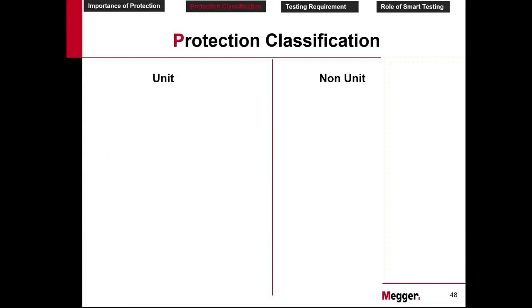So let's come back to this. You can keep this example to understand this protection classification. It's very easy. The security we are talking about is actually the relay. The relay is a protection device. It's going to protect. The compound wall, which defines the boundary of the unit in the hotel, is actually the current transformer, CT. So this is about unit protection. Unit protection means we are going to protect a specific area. And who is going to protect? The security. That security is none other than the relay. The relay is the protection unit, and it is going to protect a specific unit. That unit is defined by the CT. The area covered by the CT is the unit which we are going to protect.